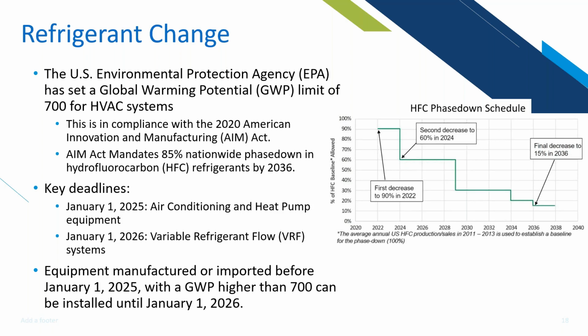For us right now, the key deadlines are: by January 1st, 2025, the global warming potential of all refrigerants we use must be below 700 for all air conditioning and heat pump equipment. And by January 1st, 2026, the same rule applies to VRF. So there's a little bit of a grace period for VRF, but it's important to understand that equipment manufactured or imported by January 1st, 2025 with a GWP higher than 700 can still be installed until January 1st, 2026. But it needs to arrive in America by January 1st, 2025, or be manufactured here by then. So it's kind of funny.